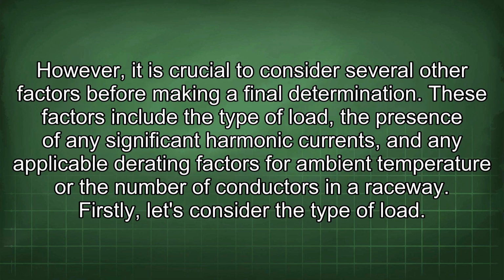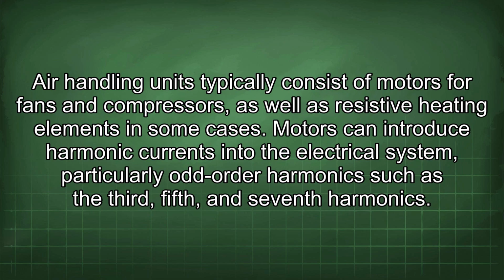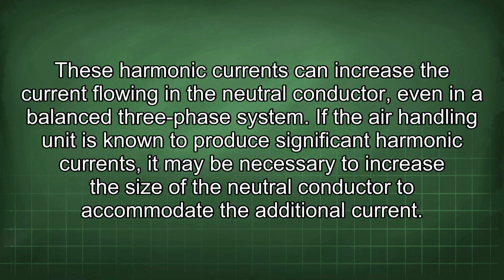However, it is crucial to consider several other factors before making a final determination. These factors include the type of load, the presence of any significant harmonic currents, and any applicable derating factors for ambient temperature or the number of conductors in a raceway. Firstly, let's consider the type of load. Air handling units typically consist of motors for fans and compressors, as well as resistive heating elements in some cases. Motors can introduce harmonic currents into the electrical system, particularly odd-order harmonics such as the 3rd, 5th, and 7th harmonics. These harmonic currents can increase the current flowing in the neutral conductor, even in a balanced three-phase system.